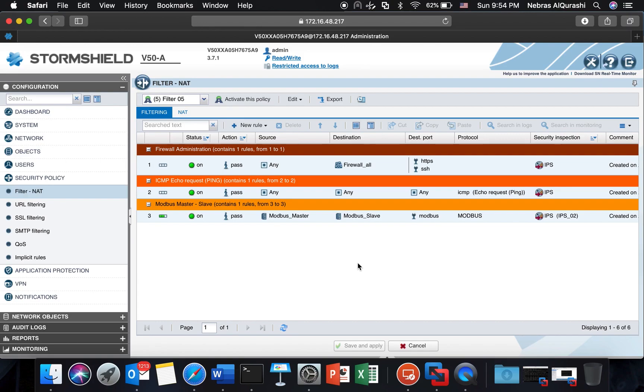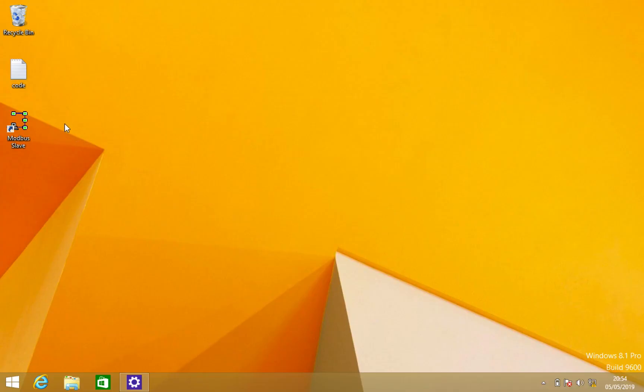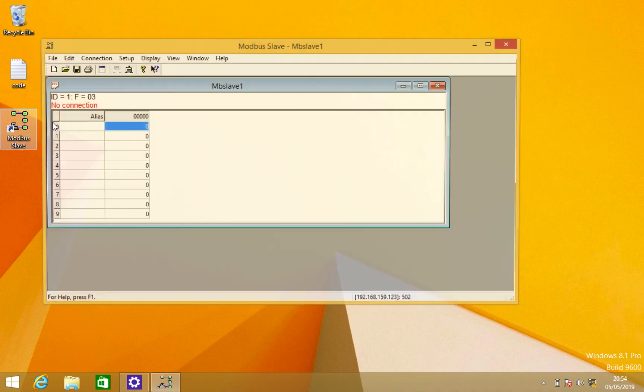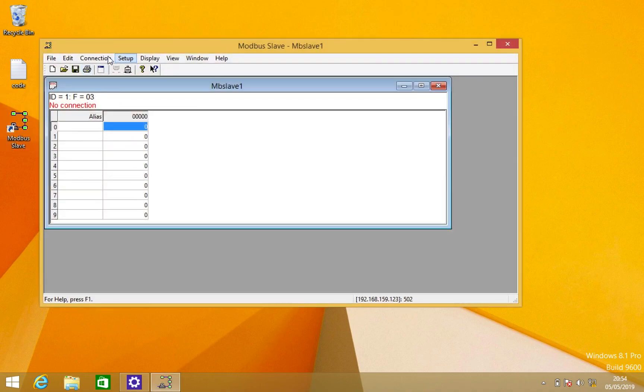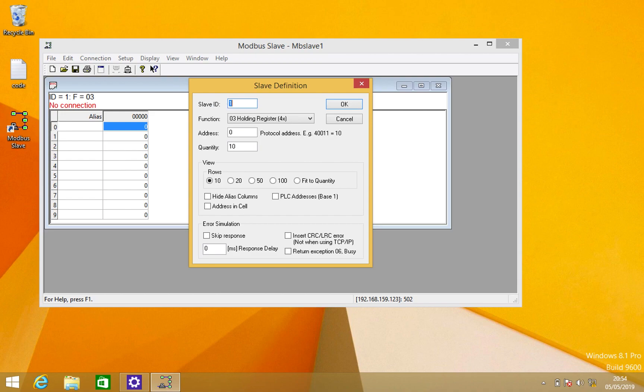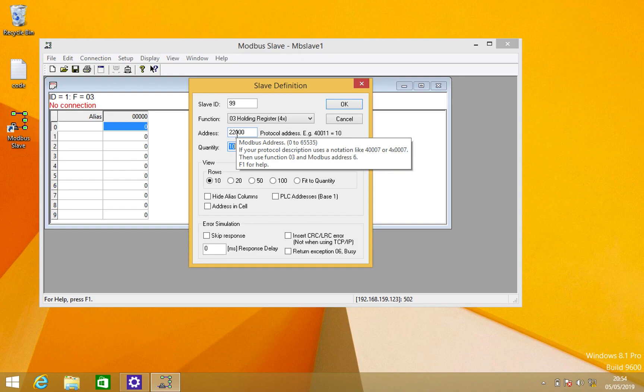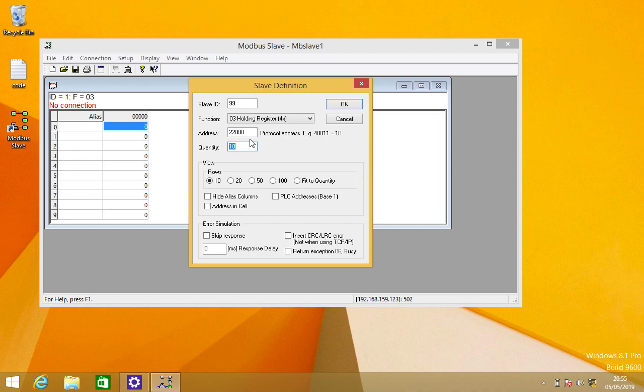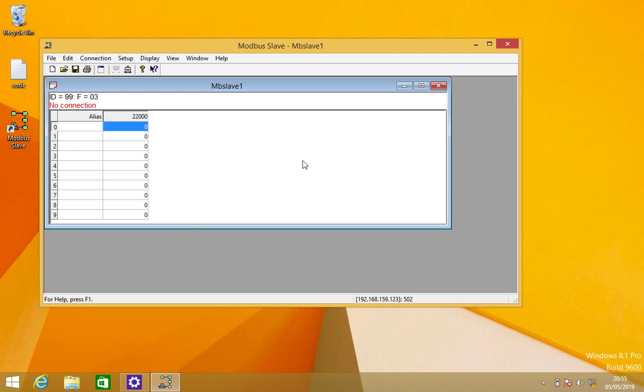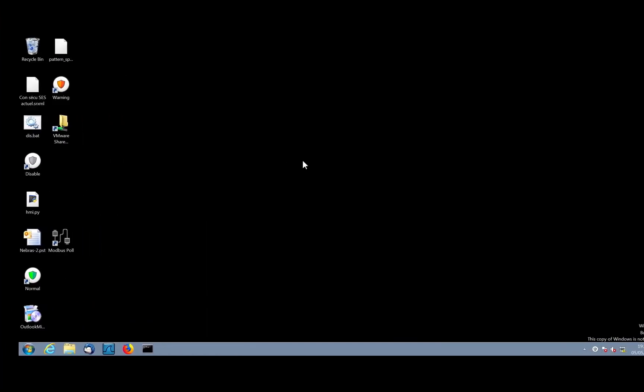Now we are good so now we can make the test. On the Modbus slave I will set up the slave. Let me set the unit ID to be something like 99. I will keep the function as 03 and I will choose the address to be from 22000 with quantity 10, so it will jump between 22000 up to 22009.